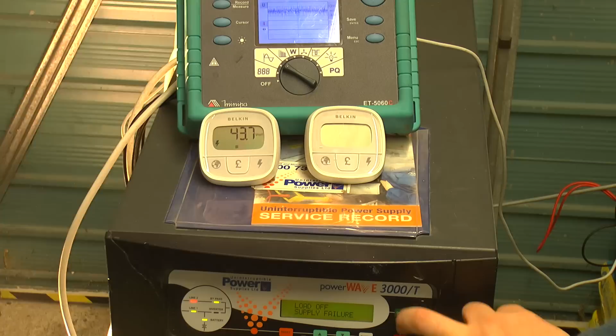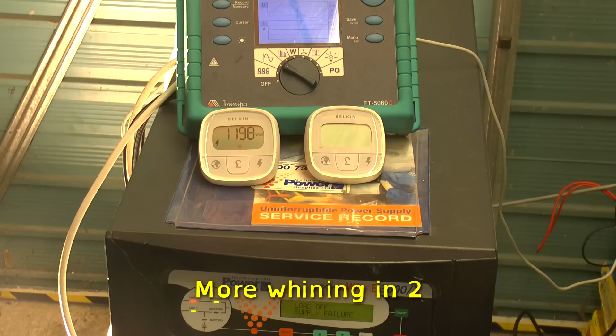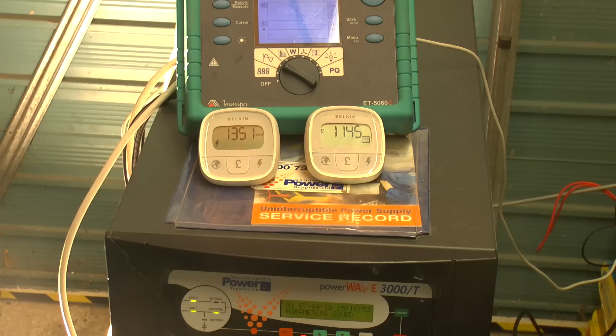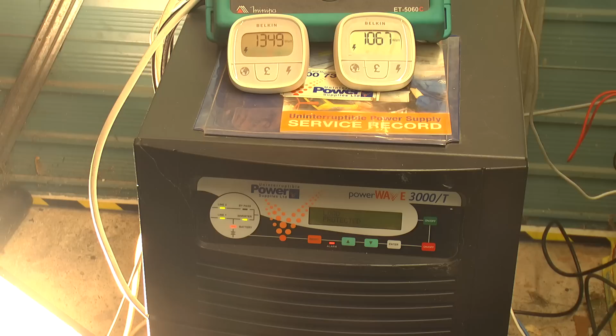If I turn it back on, is it going to grouch and say it's saving the configuration? It usually seems to. Yes. But the chargers are running at about 90 volts there, so it does seem that the minimum you can set in the menu isn't the minimum it'll go to. So if you take it to those oddball, way out of design range settings on the board, it's not going to do what you expect. So 30 batteries minimum, which if you can afford the batteries and turn fast charge on, would give you about 2.5 kilowatts of charging.